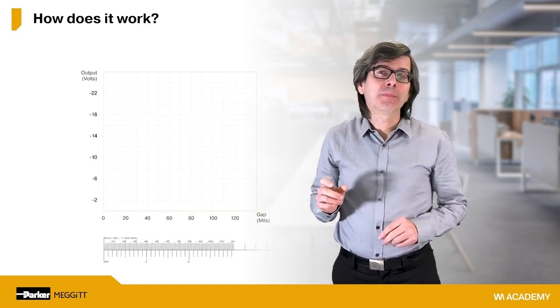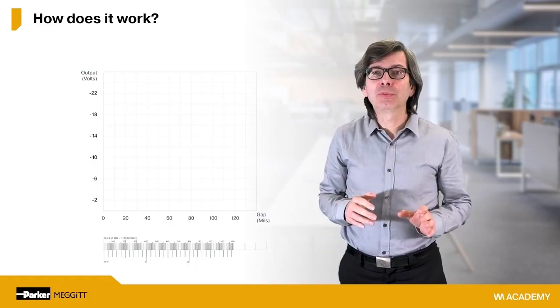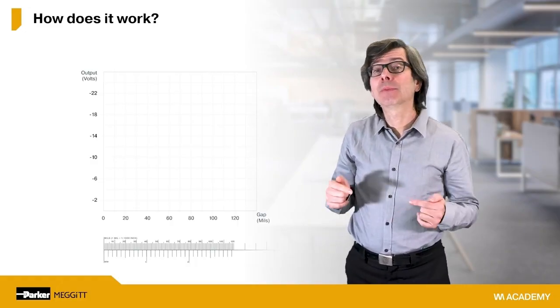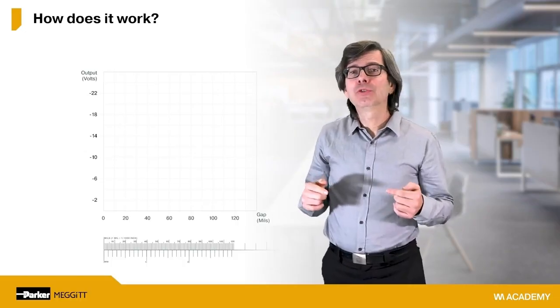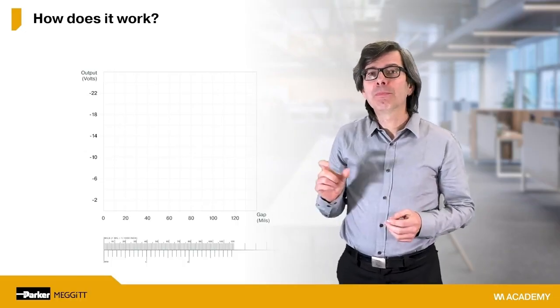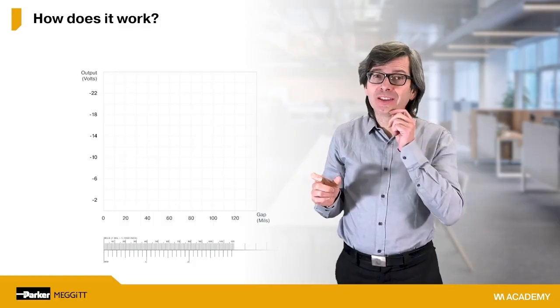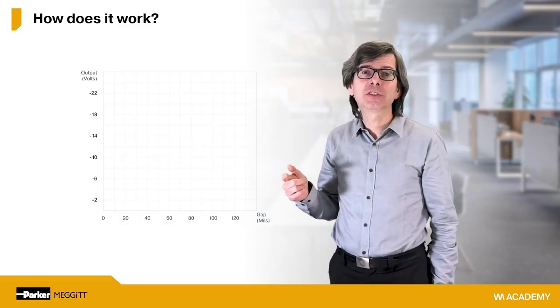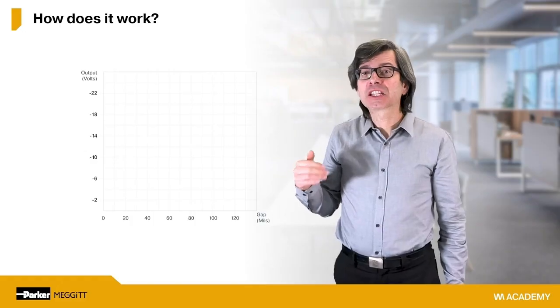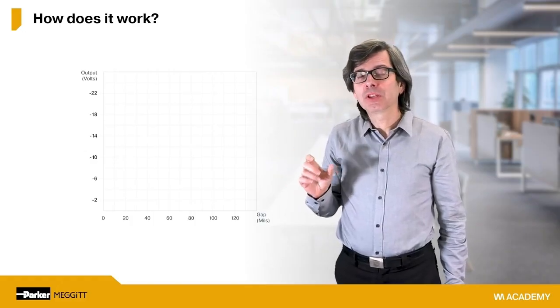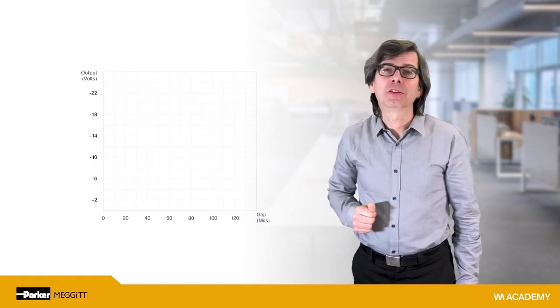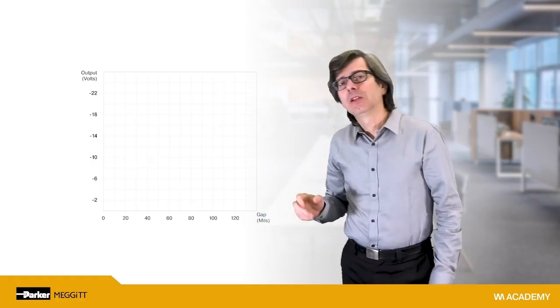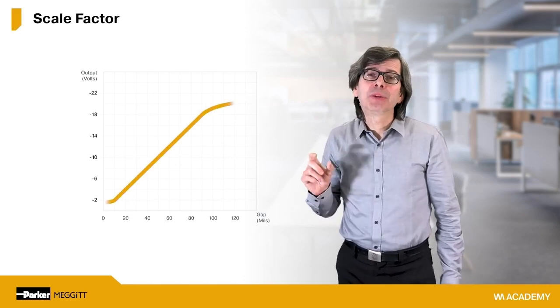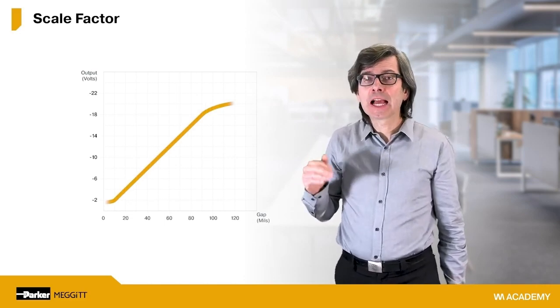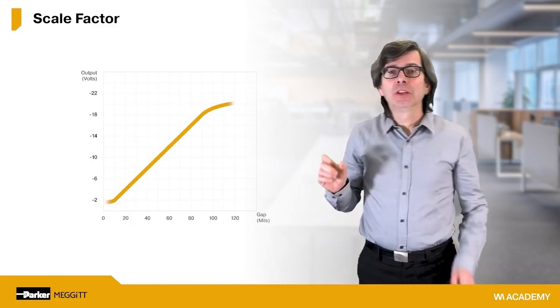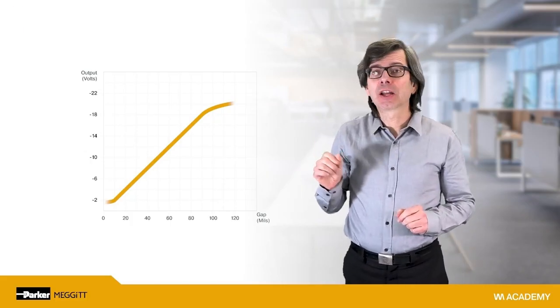Outside of North America, it is typical for the horizontal axis to be in micrometers, sometimes called microns, but we will use mils in this training because the math will be easier to do in your head than if we used metric units and a typical corresponding scale factor of 7.87 millivolt per micrometer. The scale factor simply refers to the relationship between gap and voltage. It's shown by the yellow line on the graph.